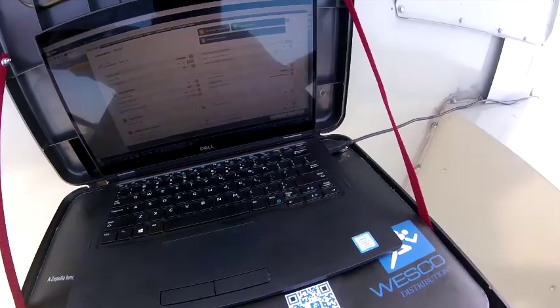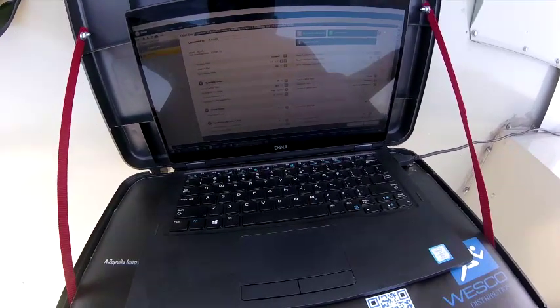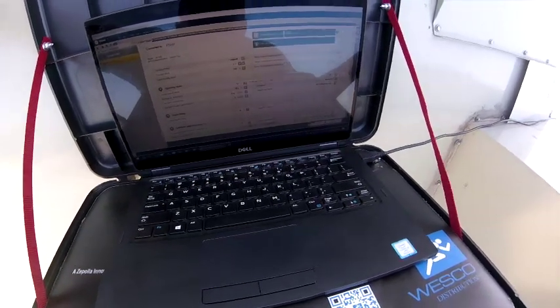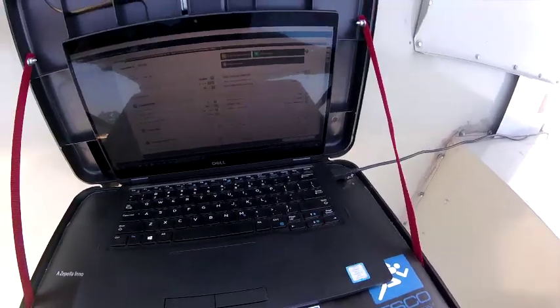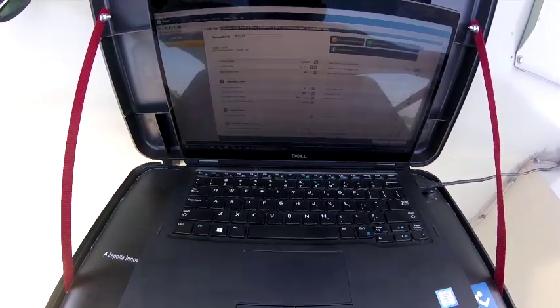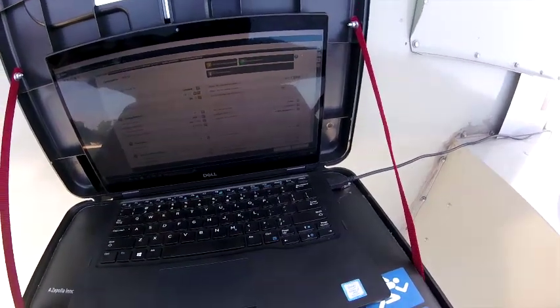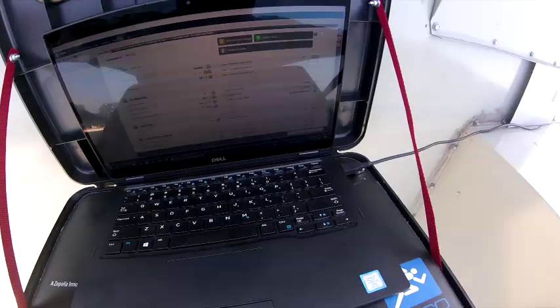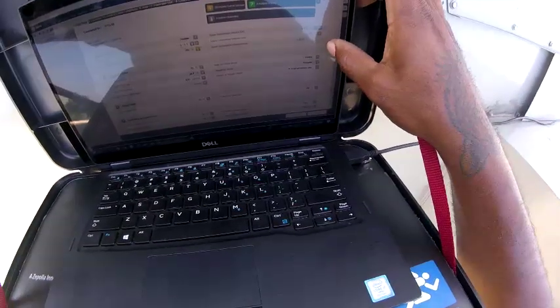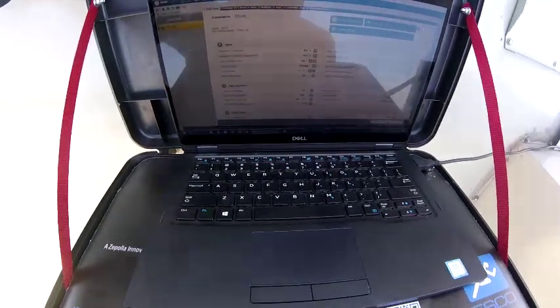So I don't know if they're having this problem in the evening time or what, but right now everything seems to be running fine. I was gonna hook up my gauges, but we got a supply temperature of 58. I'm about to call the BAS guys and see if they see anything abnormal about this. But everything looks good to me. They was complaining about high discharge temperature. That's 58. Let me check my return air temperature.